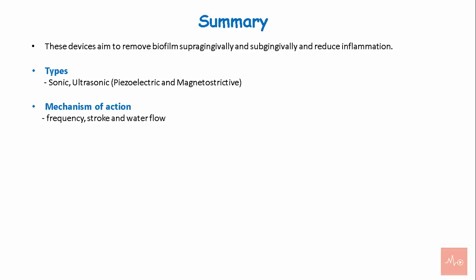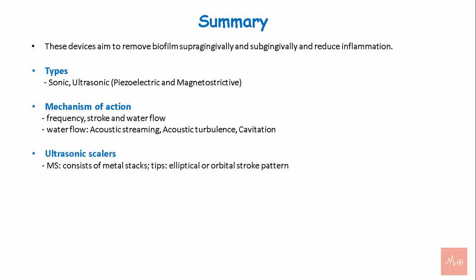The factors affecting mechanism of action are frequency, stroke, and water flow. Water flow causes acoustic streaming, acoustic turbulence, and cavitation. Magnetostrictive scalers consist of metal stacks and the tips have an elliptical or orbital stroke pattern. Piezoelectric scalers have ceramic discs and the tips have a linear stroke pattern.